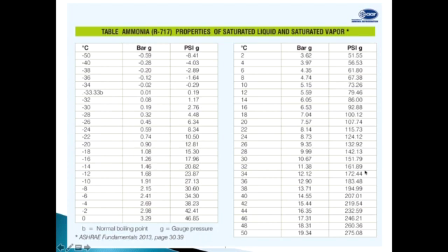So what I'm saying here is that if your purger discharge temperature or your condensing temperature and pressure are maintained at the rated condition and there is no increase in the discharge pressure, it means your purger is working. If a purger is removing air continuously for, say, 1 month, that is not correct. It means there are leakages in the plant and air is continuously entering. Somewhere down the line, your purger must stop working and the discharge pressure should remain as per the design conditions and guidelines.